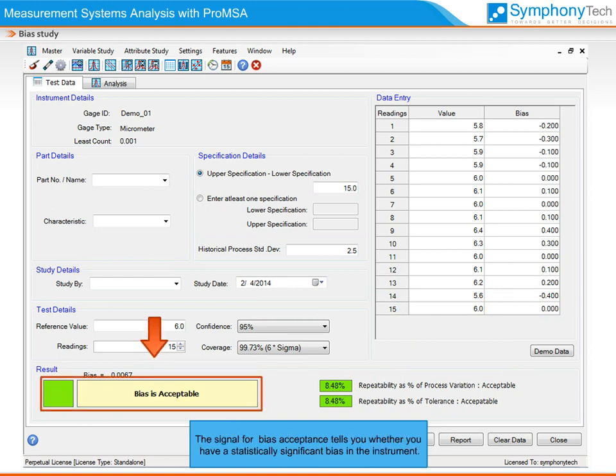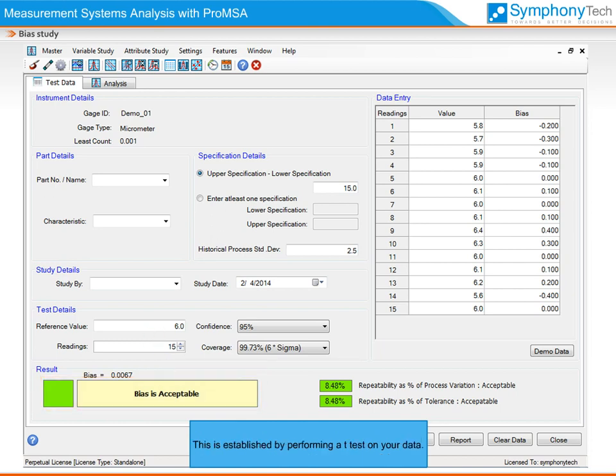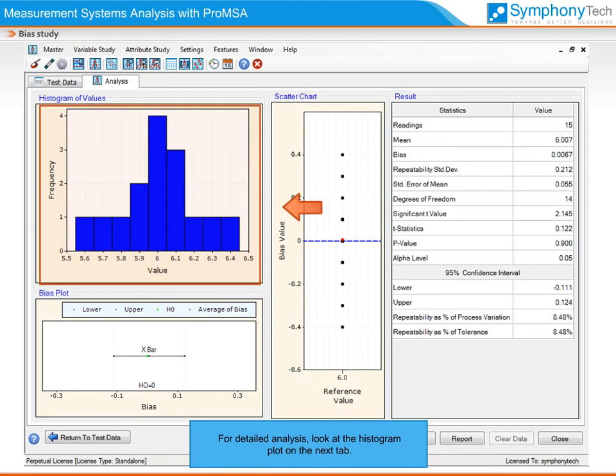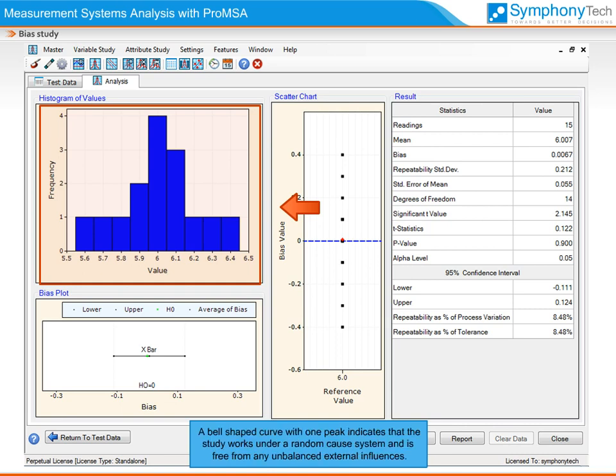The signal for bias acceptance tells you whether you have a statistically significant bias in the instrument. This is established by performing a t-test on your data. A significantly high bias is unacceptable. For detailed analysis, look at the histogram plot on the next tab. A bell-shaped curve with one peak indicates that the study works under a random cause system and is free from any unbalanced external influences.